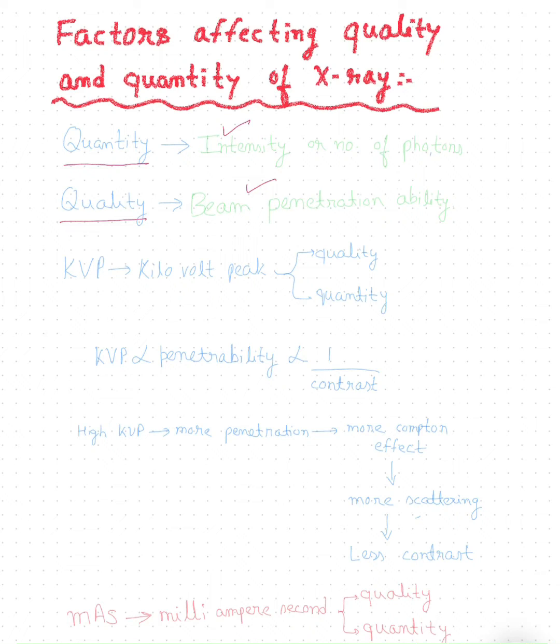The first and most important factor is kilovolt peak, or KVP. This KVP affects both quality and quantity of the X-ray beam. KVP is directly proportional to the penetrability of the X-ray beam and inversely proportional to the contrast of the X-ray film.